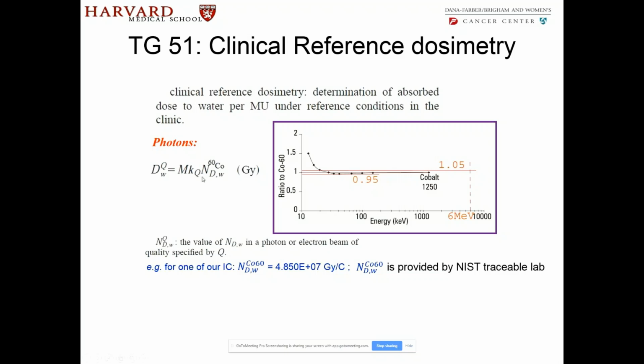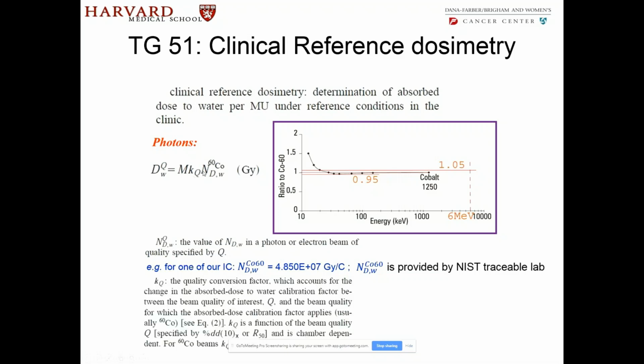So you have your ion chamber, you send it out, and it comes back with a calibration curve, with a calibration number for cobalt. But looking at this curve, you know that the ion chamber is energy dependent. As a result, you need to make some sort of correction to allow for 6 MeV energy. That part, an additional calibration factor, a correction factor, is what this KQ is. So this quantity here comes to you from the NIST traceable lab. But KQ is something that you have to measure for your machine. It's called the quality conversion factor.